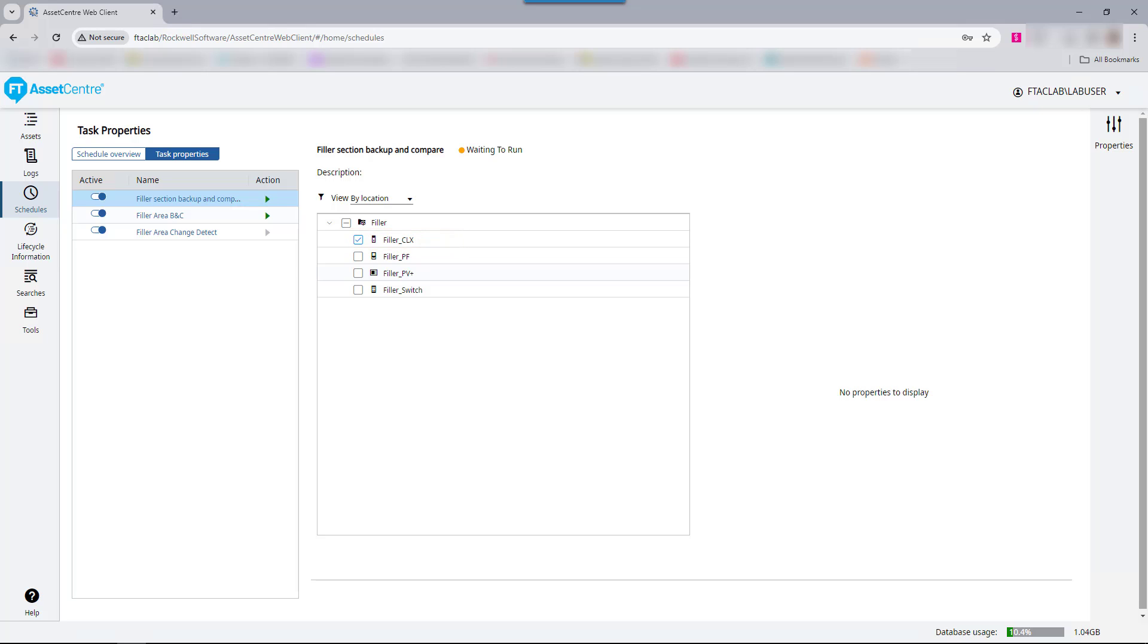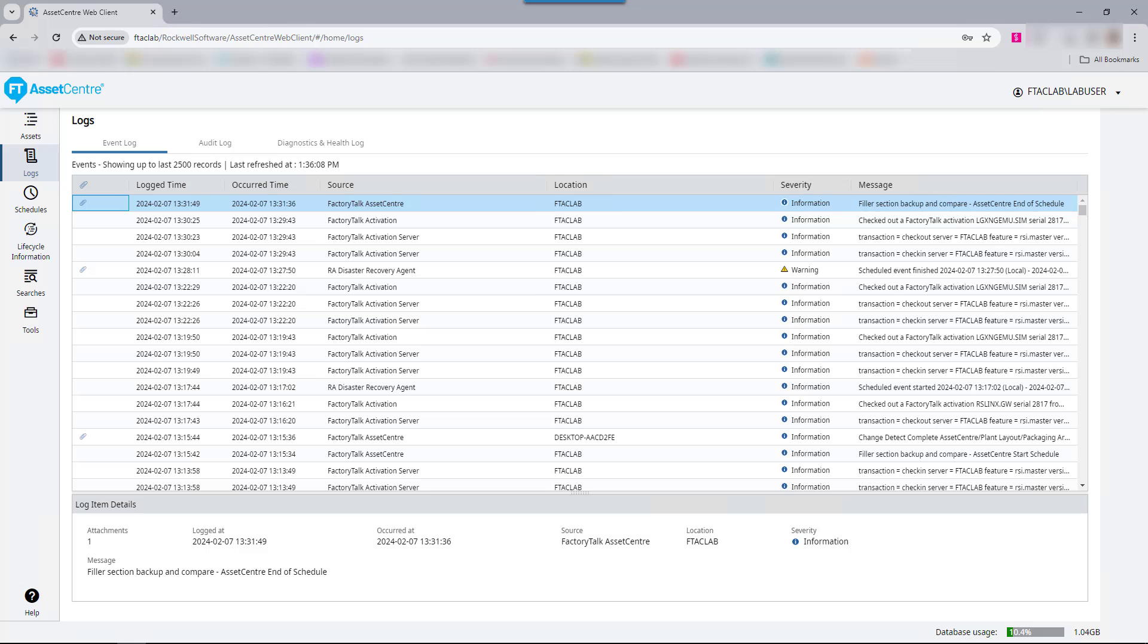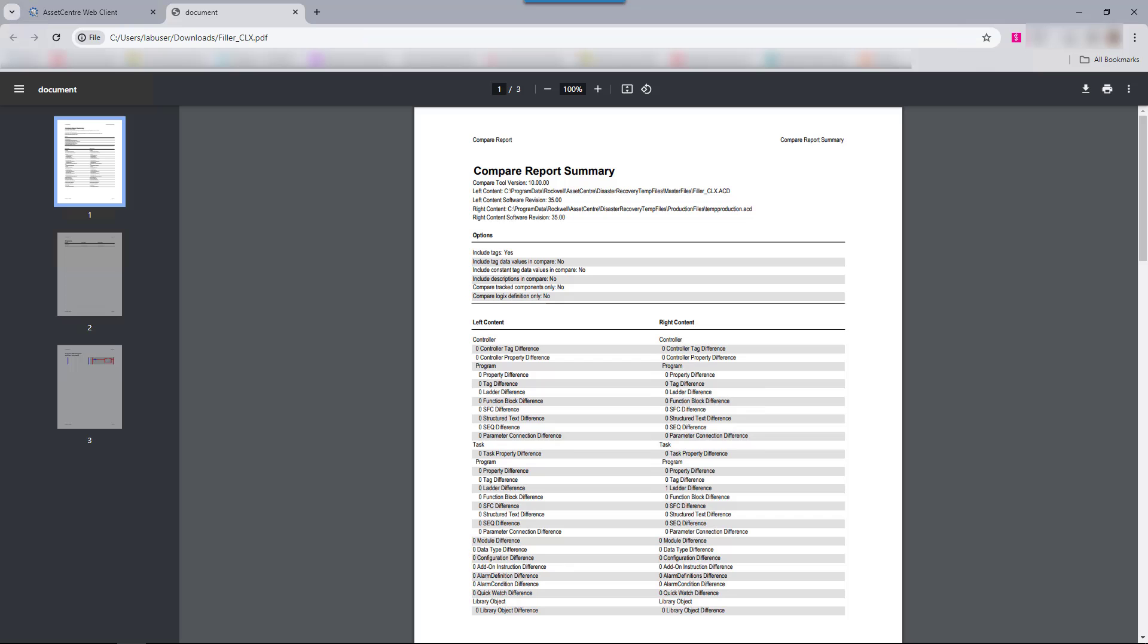If differences were found, the differences report has been emailed based off the configuration that we set up. However, it is also stored in the Factory Talk Asset Center logs. Logix 5000 assets use the Logix Designer Compare Utility, which outputs detailed comparison information. The first page of the comparison report shows a high-level overview of the changes. Under the task section, we can see that there is one rung difference on the right content, which is the online value, which is different from the offline project designated as the left project.